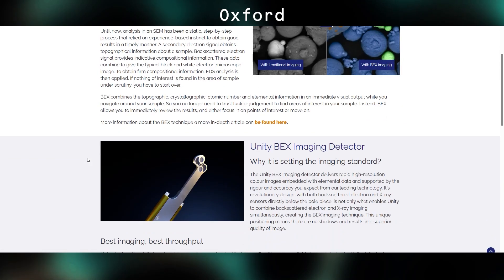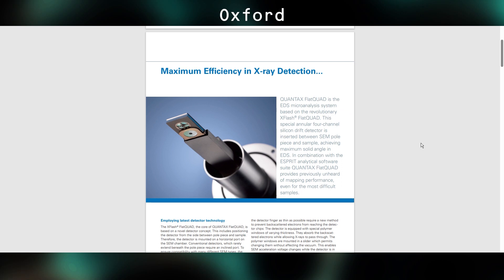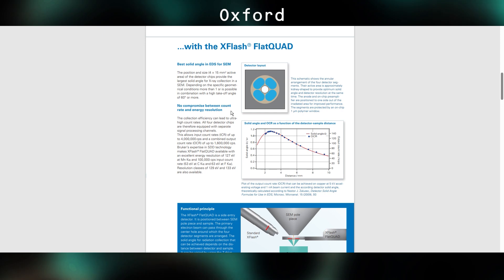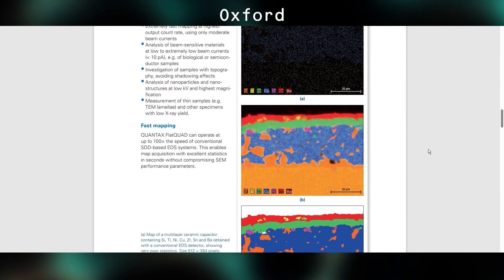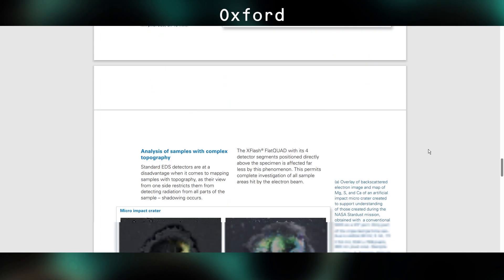To do that I'm going to have to start with a little background info. I could be wrong on these dates, but I think around six years ago Bruker released the Flat Quad, which is an EDS detector that comes into the chamber parallel to the ground and has four 15mm detectors sitting directly above your sample. This has some incredible benefits for data collection. First off, you get millions of counts per second — their brochure says up to 4 million — since the detector is much closer to your sample and also completely surrounding your sample. This means you can get a statistically relevant number of counts in a map to do reliable quantification analysis that won't take you a week to collect. The other really great thing is that because the detector is right over the sample, there are no shadows in the map — you can actually get EDS data out of a hole. Lastly, with a very beam-sensitive sample, you can severely restrict the current hitting the sample and still get what would otherwise be considered a normal number of counts.